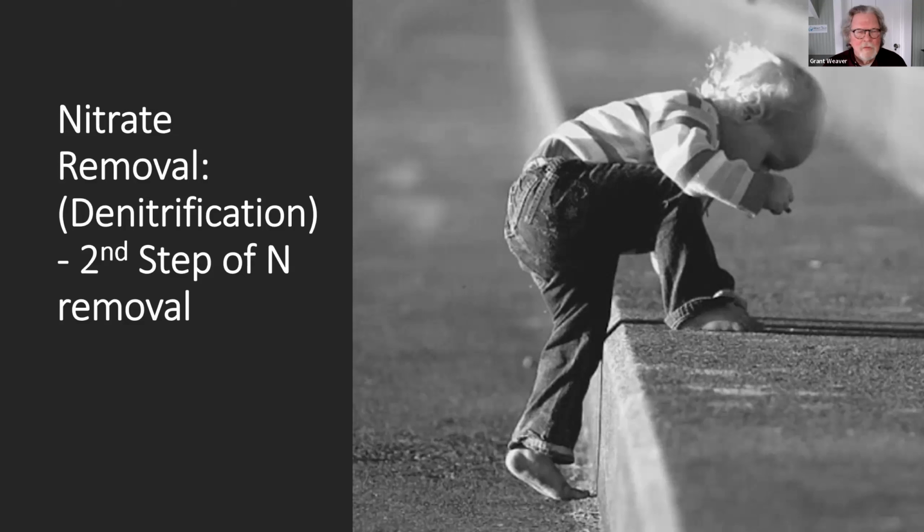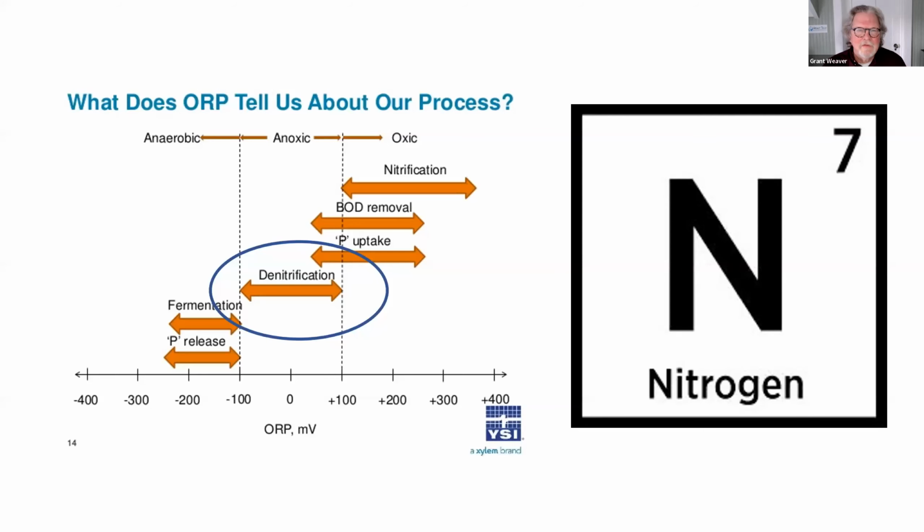So we want to control total nitrogen more and more now. You're seeing it more and more in permits. To complete that is a low oxygen environment. So if you have an ORP, I usually start with a target of -100. I've seen plants that do quite well in that positive 100 number here, but more often than not, I like to see that number less than 0. The dissolved oxygen that's in the textbooks will tell you 0.3 or less, so really low dissolved oxygen.